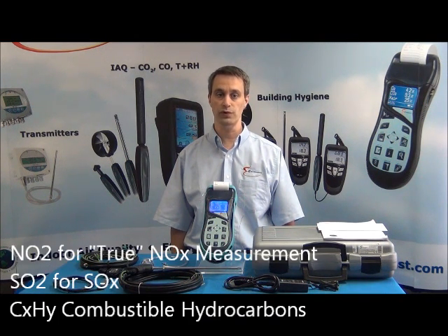The E4400 can be configured to have a maximum of 4 gas sensors. The first 3 gas sensors are typically oxygen, CO, and NO for NOx. If a 4th gas sensor is required, the sensor options are NO2 for a true NOx measurement, SO2 for SOx, and CxHy combustible hydrocarbons. The 4th gas sensor can be installed when the E4400 is first purchased, or it can also be added as an upgrade at a later time.